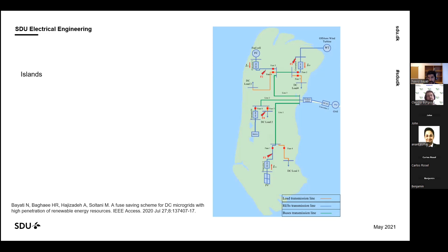In microgrids, DC or AC, for sure we will have different control and protection components. Every resource, wind turbines, PVs, should have some frequency controller, because if we work in islanded mode, and we're talking about the AC microgrid, for sure the frequency of the system should remain constant. So the frequency should remain at 50 Hertz.